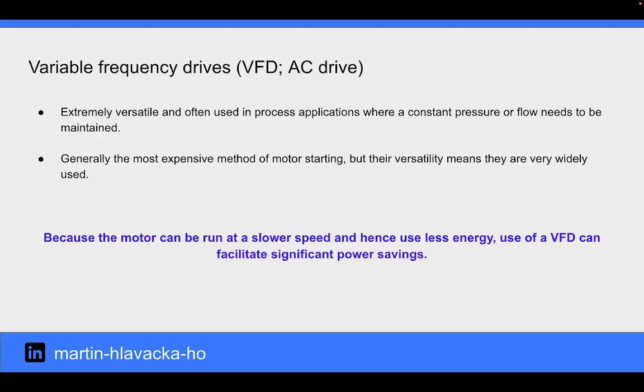A VFD is extremely versatile and often used in process applications where constant pressure or flow needs to be maintained. In addition, because the motor can be run at a slower speed and hence use less energy, the use of a VFD can facilitate significant power savings. Variable speed drives are generally the most expensive method of motor starting, but their versatility means they are very widely used.